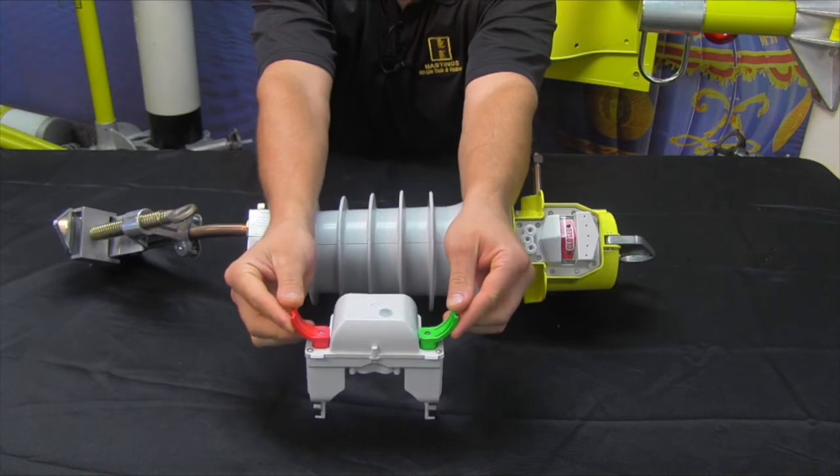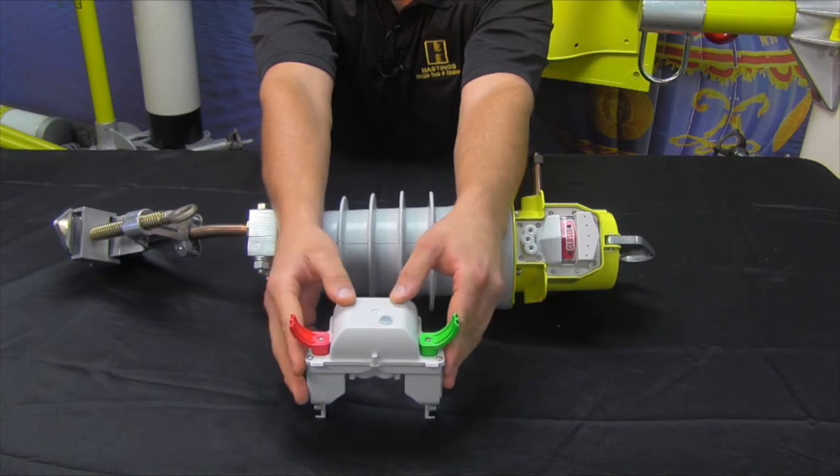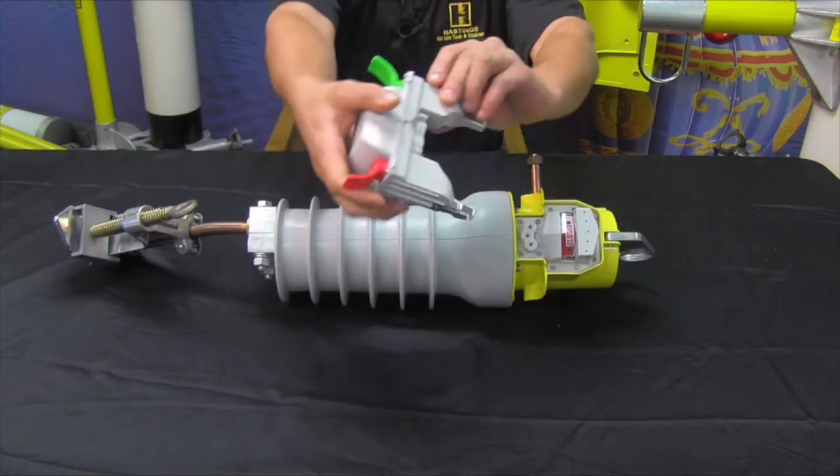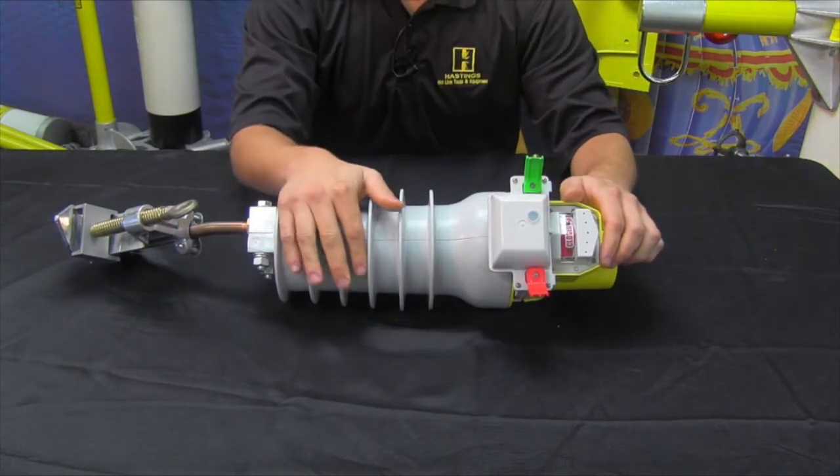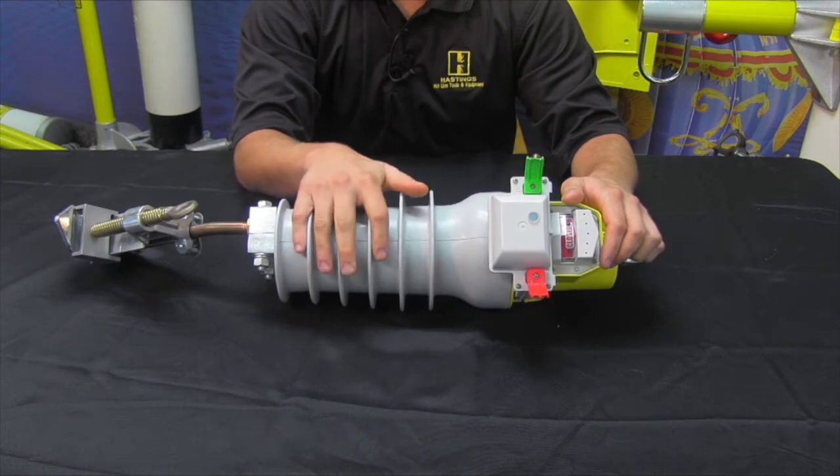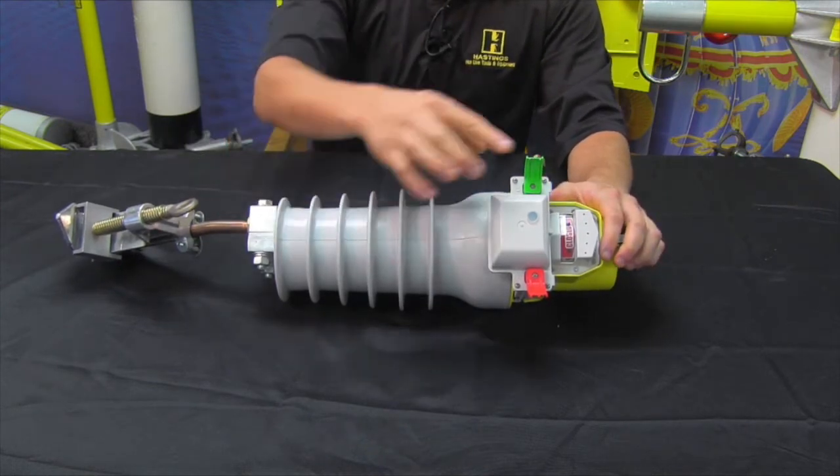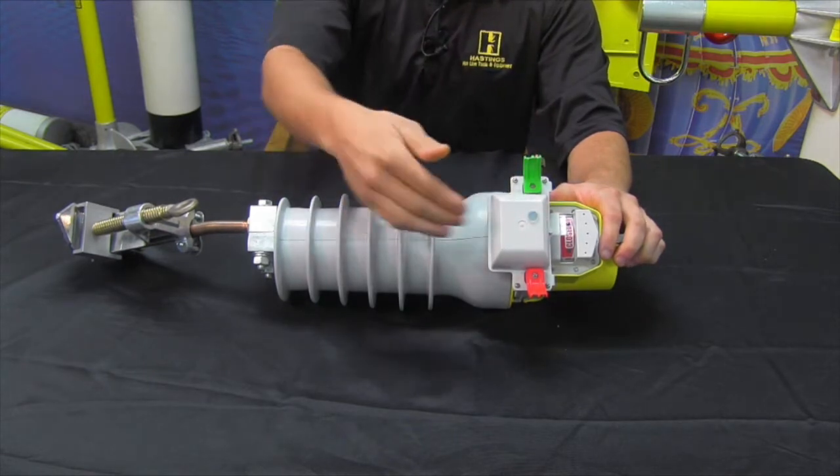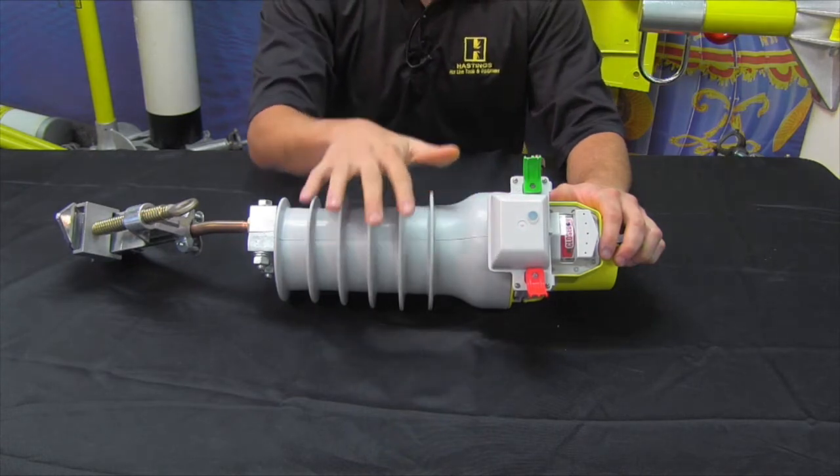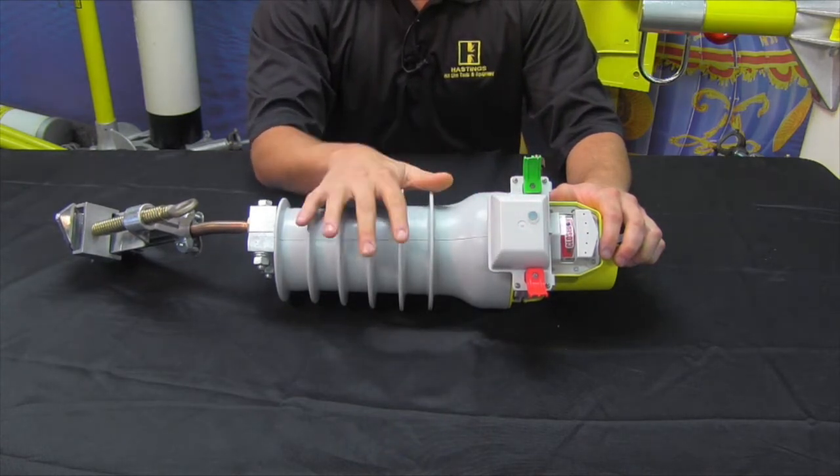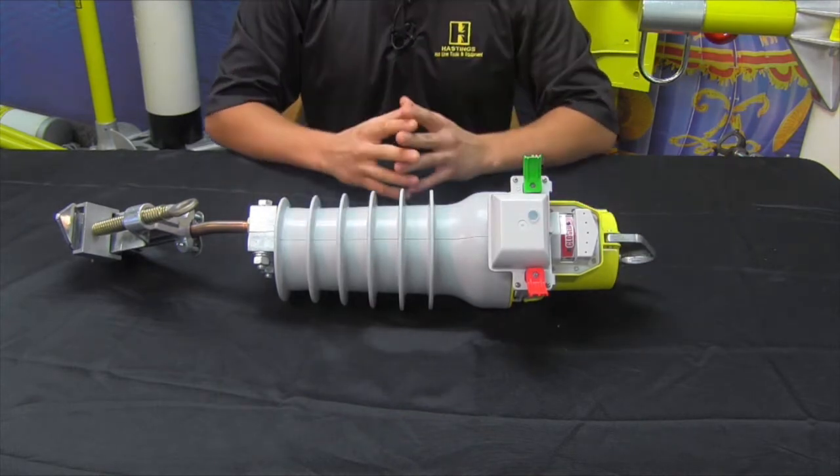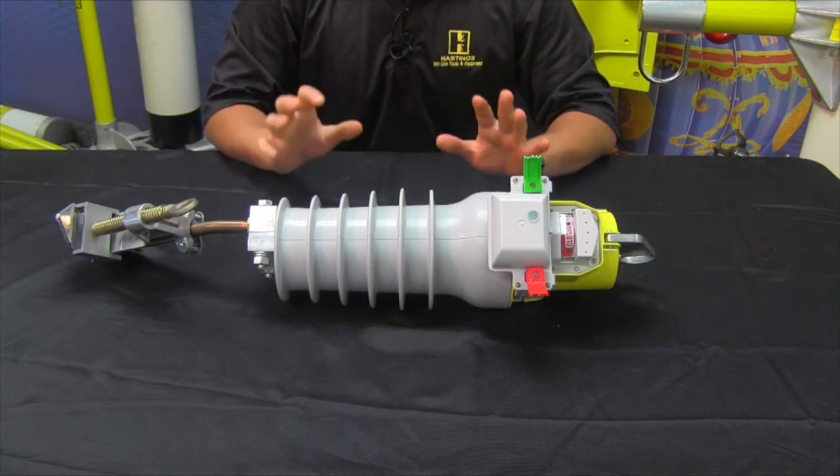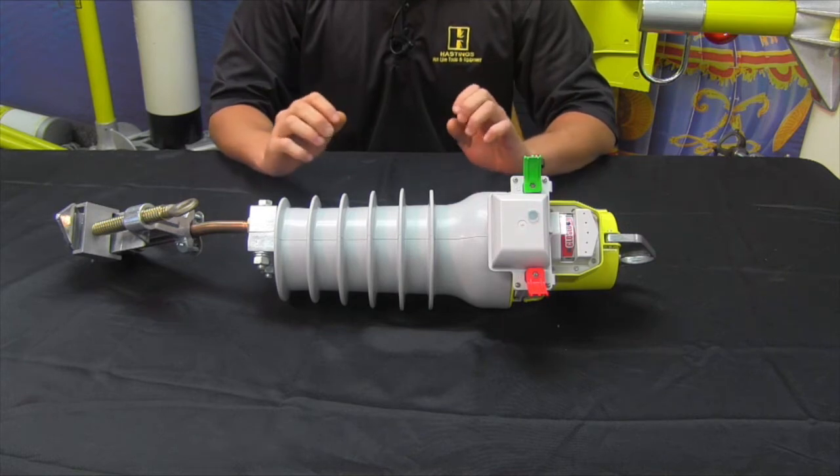Next you'll notice these two tabs here, one green, one red. These are actually buttons that tell your device which function to operate. For example, I've hung this on a closed circuit and I want to go ahead and open it and break my load. All I need to do once my setup is complete is press this green button here. Now you can see this light will begin to blink, and what this is is a 60 second safety window. So that means I have 60 seconds to go ahead, back away, create a distance, make sure everything is still ready to go and let the switch do all the work. Now let's say for instance, for any reason I don't want that switch to go ahead and open, all you need to do is pull this lever here.